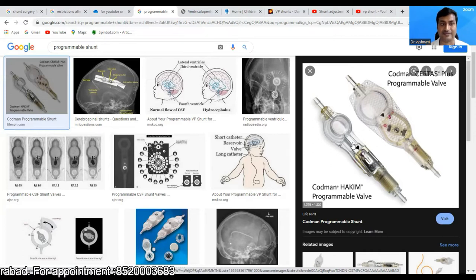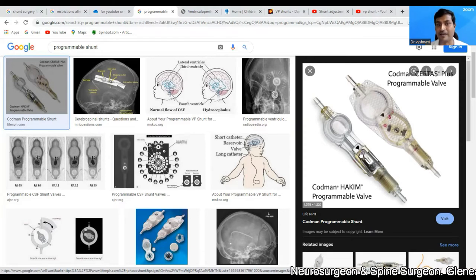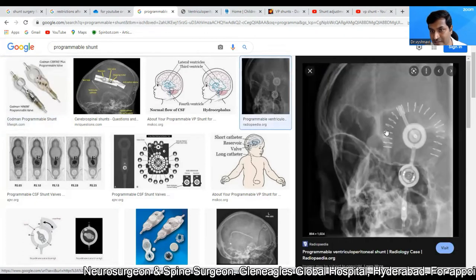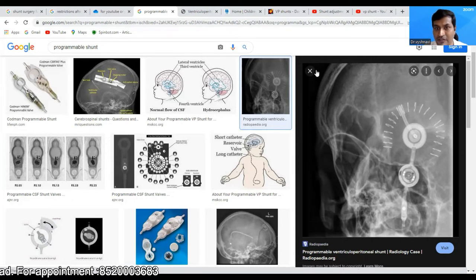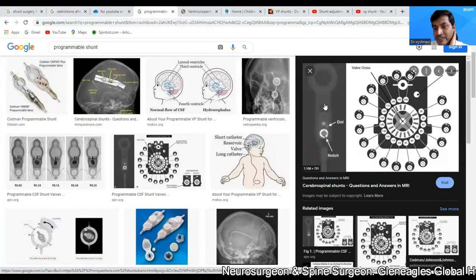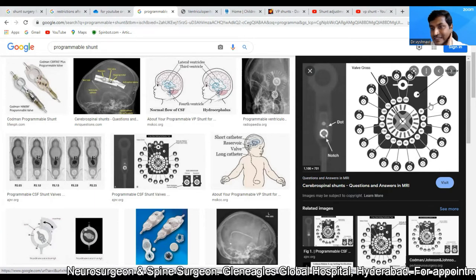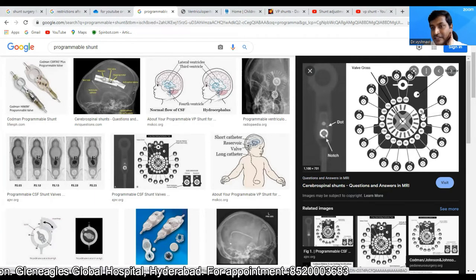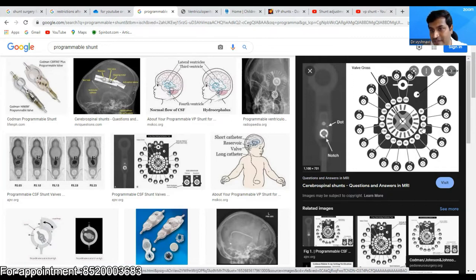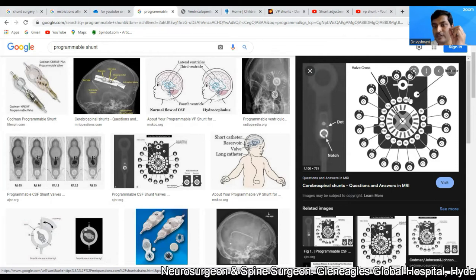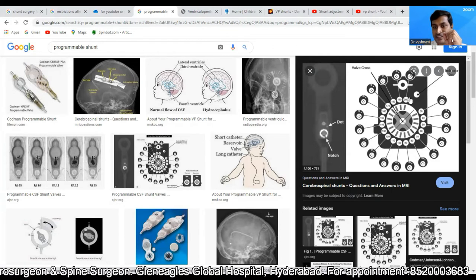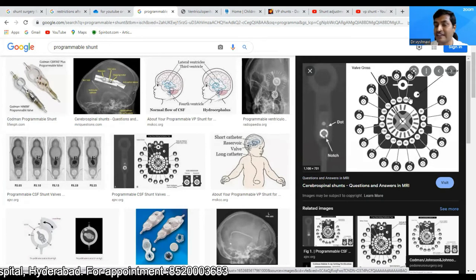What is a programmable shunt? This is a Codman programmable valve. This valve is programmable — I will show you a picture. This is the valve after implantation. You can see the pressures within the valve can be set at 30, 40, 50, 60, 70, 80, 90 up to 200 mm. You can pinpoint and adjust the pressure without any surgery, and the adjustment of pressure hardly takes five minutes. If the shunt is over draining, we increase the pressure higher. If the shunt is under draining, we decrease the pressure lower.